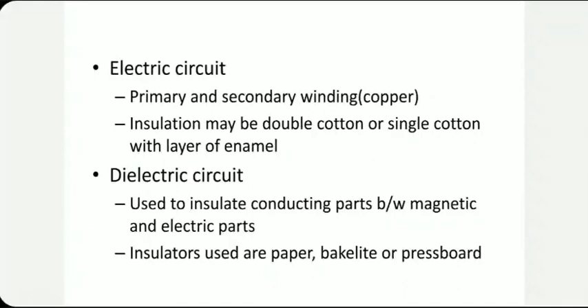The windings are normally made of copper. Aluminum is not used because cost is not such a major issue. In transmission lines, we use aluminum because you have kilometers and kilometers of lines. In transformers, the length of the wire is not that large, so you can go for copper and reduce losses. Copper has better electrical conductivity, and actually better thermal conductivity too, but right now I'm not interested in thermal conductivity.